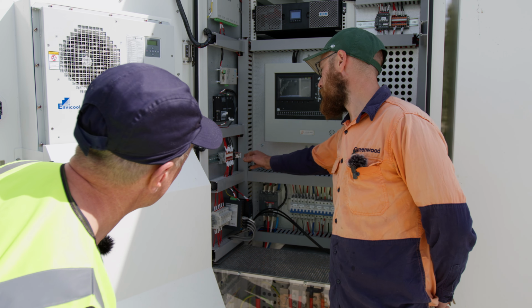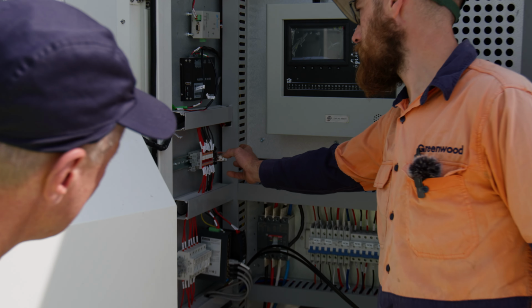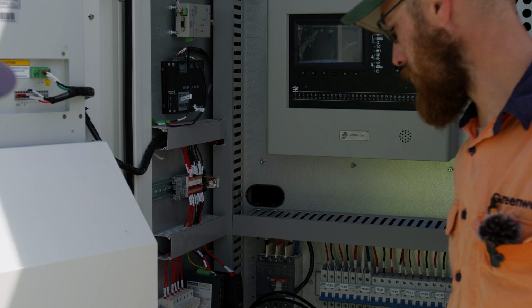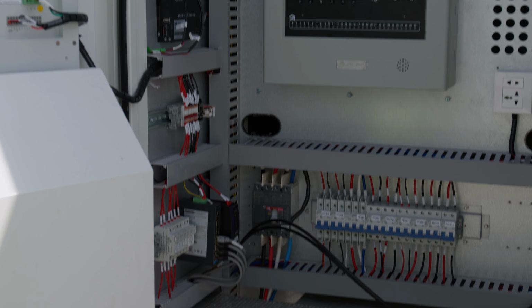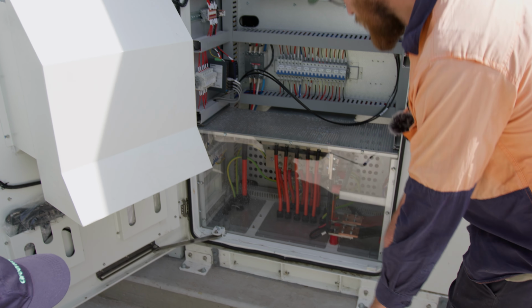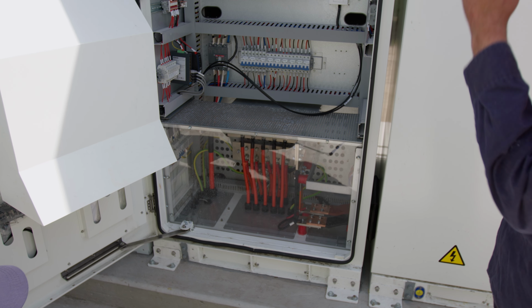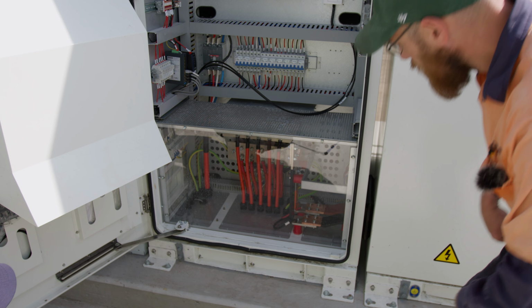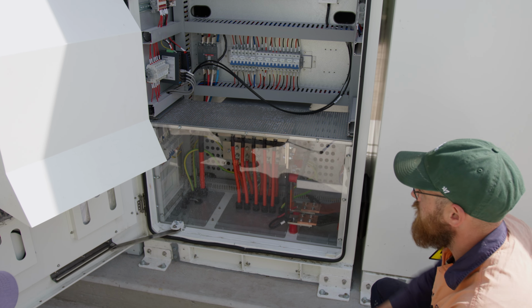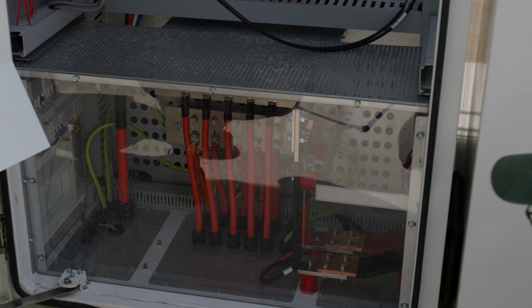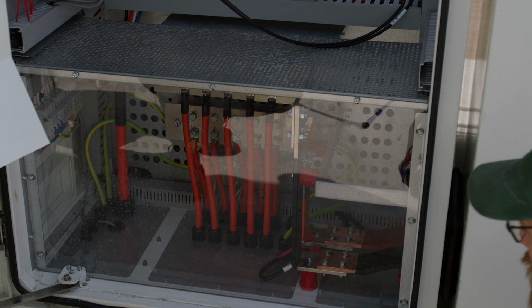It also puts 24 volt up to control this relay. It's part of the control gear for the system. Now, we're coming down to the bottom of this cabinet. Obviously, there's a large piece of perspex covering everything. Perspex is there for touch voltage because there's no other way to protect the main bus bars behind there. This is where this kind of system is different to a lot of other BESS systems.